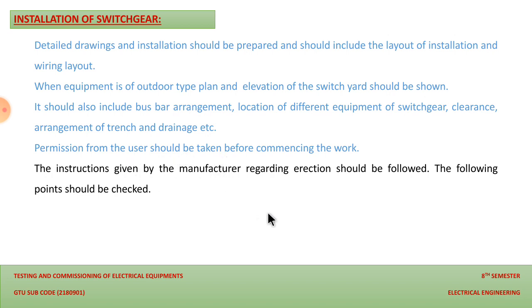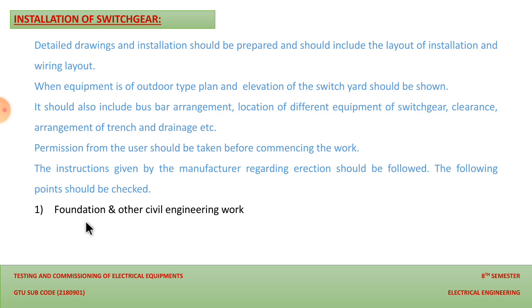And the points that we should follow while erecting the switchgear are shown with the numbers over here. The first point that we should follow is foundation and civil engineering work. We are talking about industrial equipment, and these equipments are very large, and the operation of these instruments involves vibrations, and we have to protect these instruments from other factors like water, oil, and other contamination, say acid and gases. So a proper foundation and civil work is necessary for such switchgears. We have to check this point first, that the proper foundation and the proper civil engineering work has been done for the installation of the switchgear.